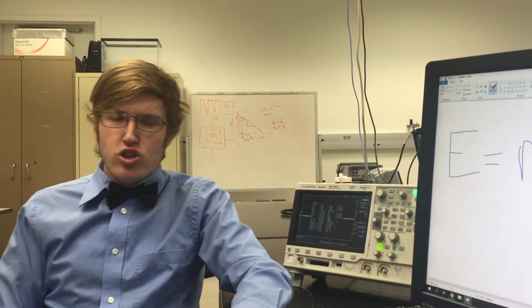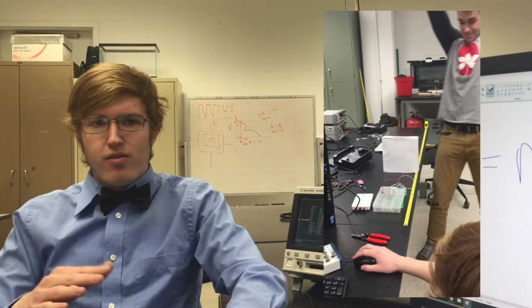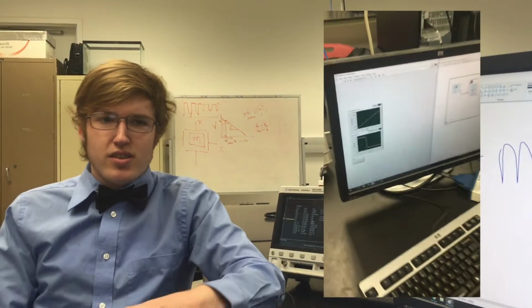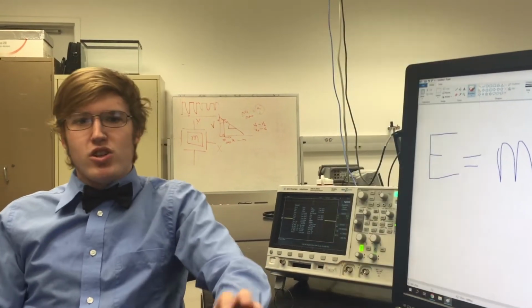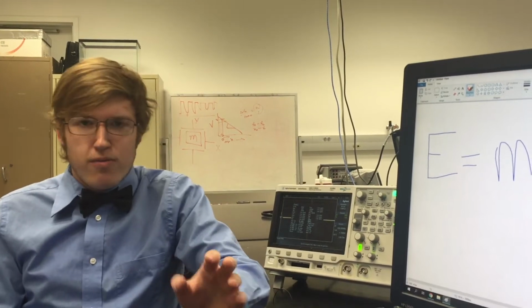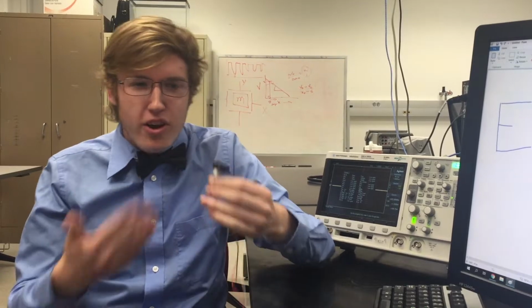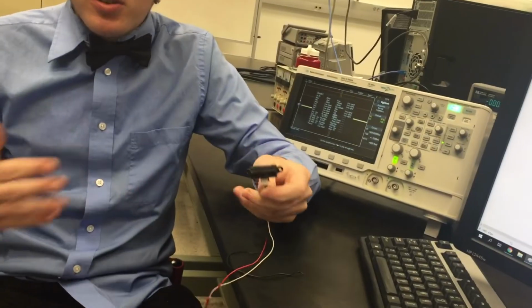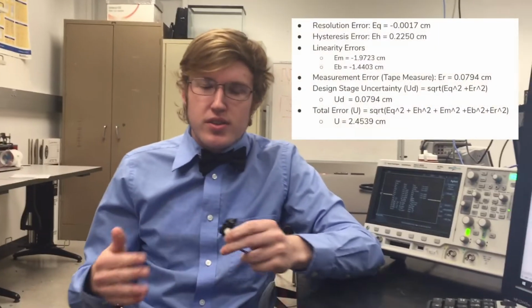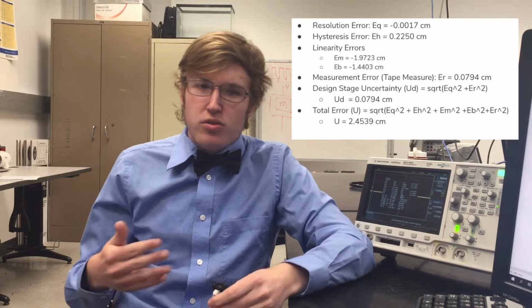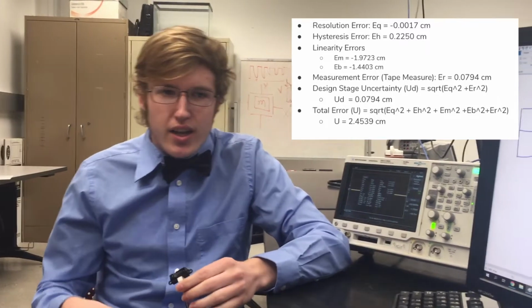For the dynamic calibration, two boxes were placed one in front of the other, and data was collected as the first box was removed from the second box. This sensor works effectively from 1.5 inches to 12 inches, or approximately 4 to 30 centimeters. And now for the specific details regarding this beautiful sensor. So the resolution error came out to be about 0.0017 centimeters for our data acquisition system. The hysteresis error came to be about 0.2250 centimeters from our static calibration.